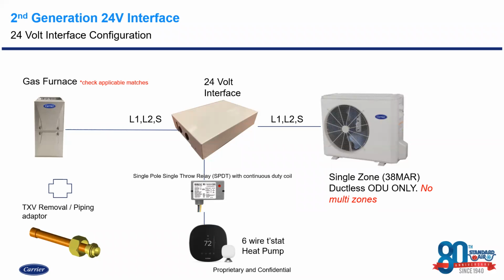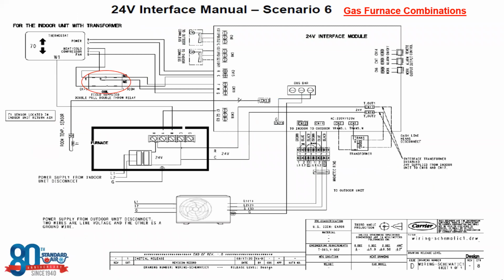So, we have an outdoor unit, a 24-volt interface, an applicable gas furnace, a TXV removal piping adapter, a single pole, single throw relay, and then a 6-wire heat pump thermostat. So let's look at that from a wiring perspective. You'll see a lot of similarities on here with the actual FB models. Of course, we have our field supplied single pole double throw relay.